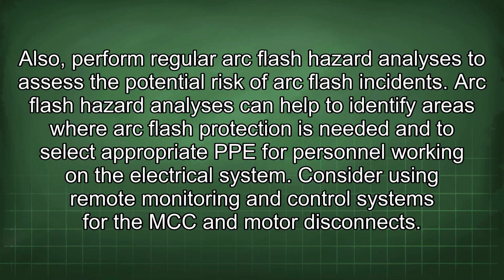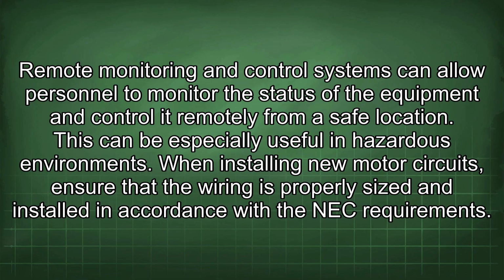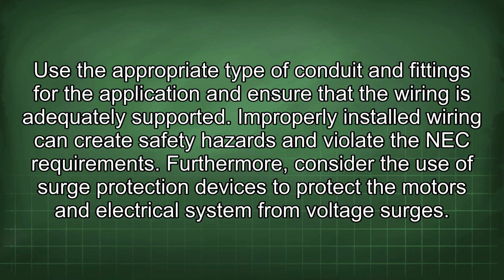Consider using remote monitoring and control systems for the MCC and motor disconnects. Remote monitoring and control systems can allow personnel to monitor the status of the equipment and control it remotely from a safe location. This can be especially useful in hazardous environments. When installing new motor circuits, ensure that the wiring is properly sized and installed in accordance with the NEC requirements. Use the appropriate type of conduit and fittings for the application and ensure that the wiring is adequately supported. Improperly installed wiring can create safety hazards and violate the NEC requirements.